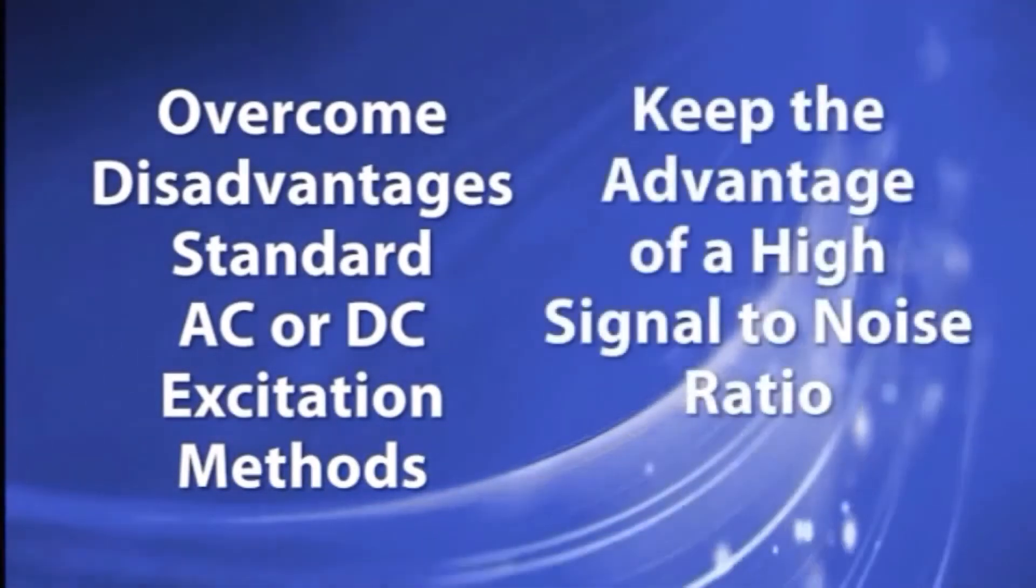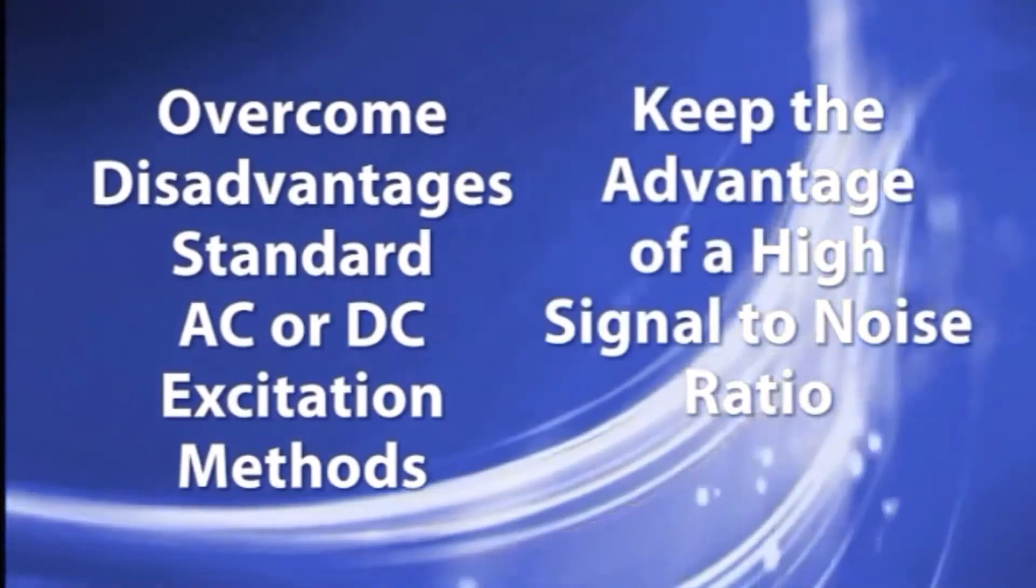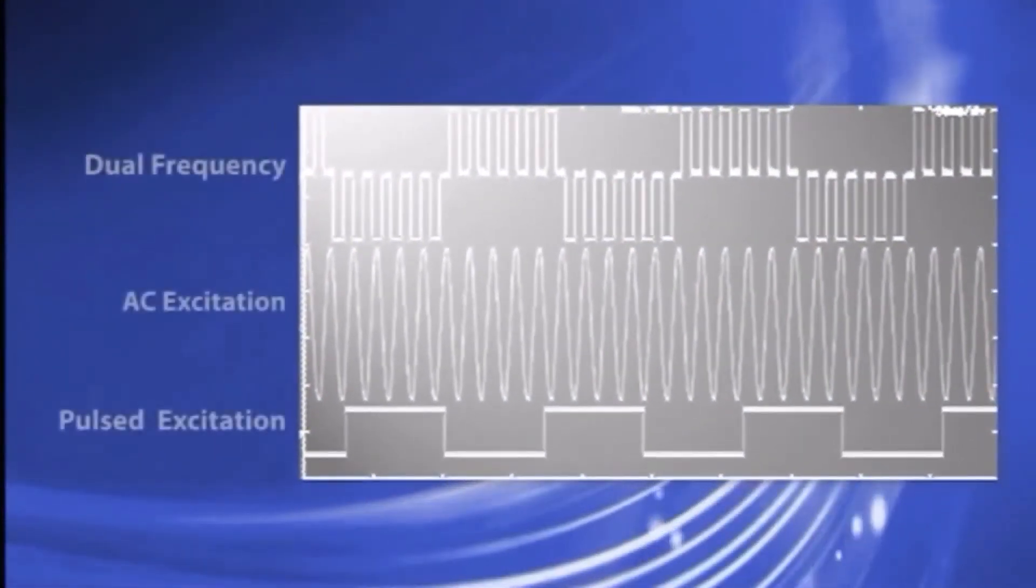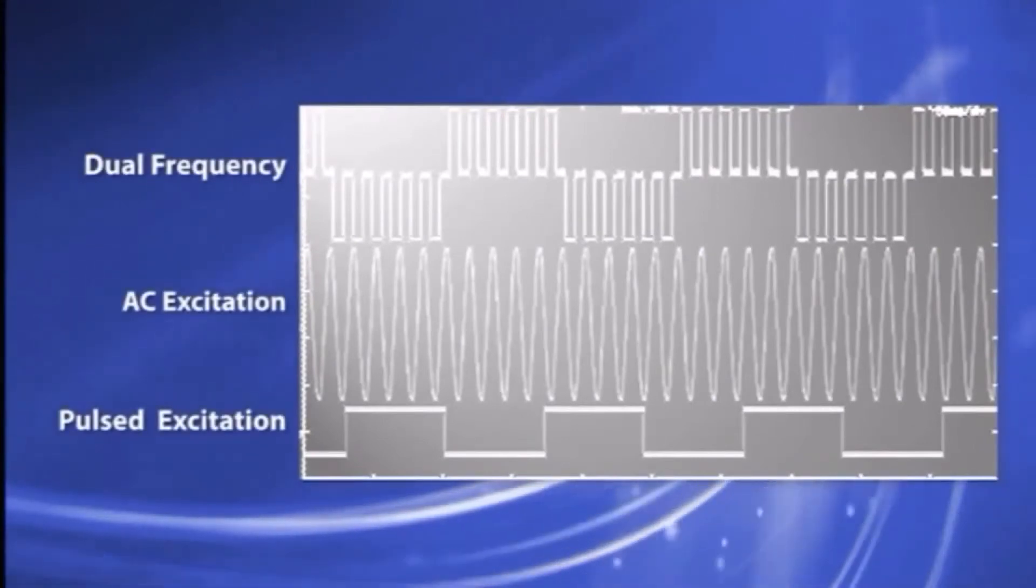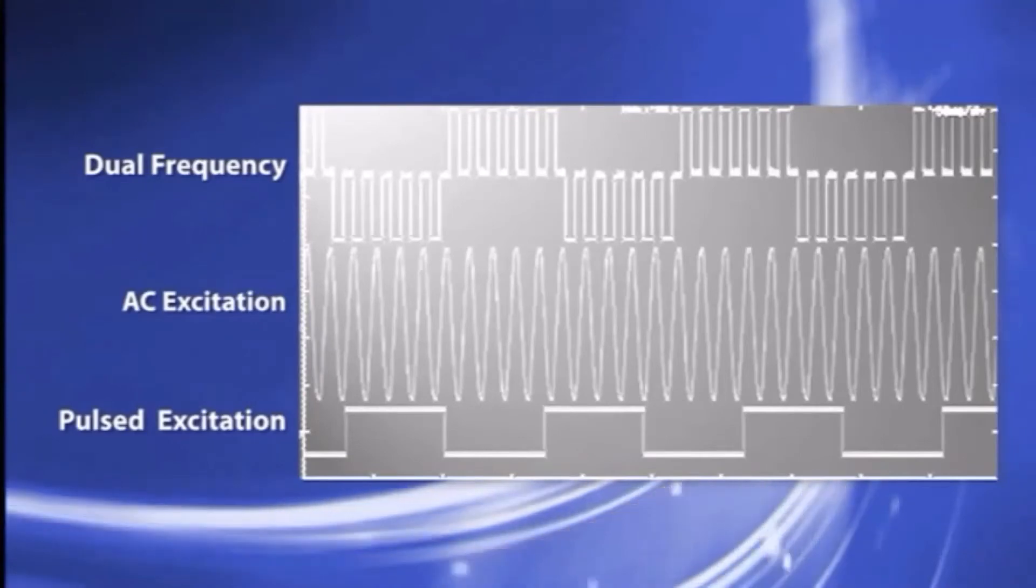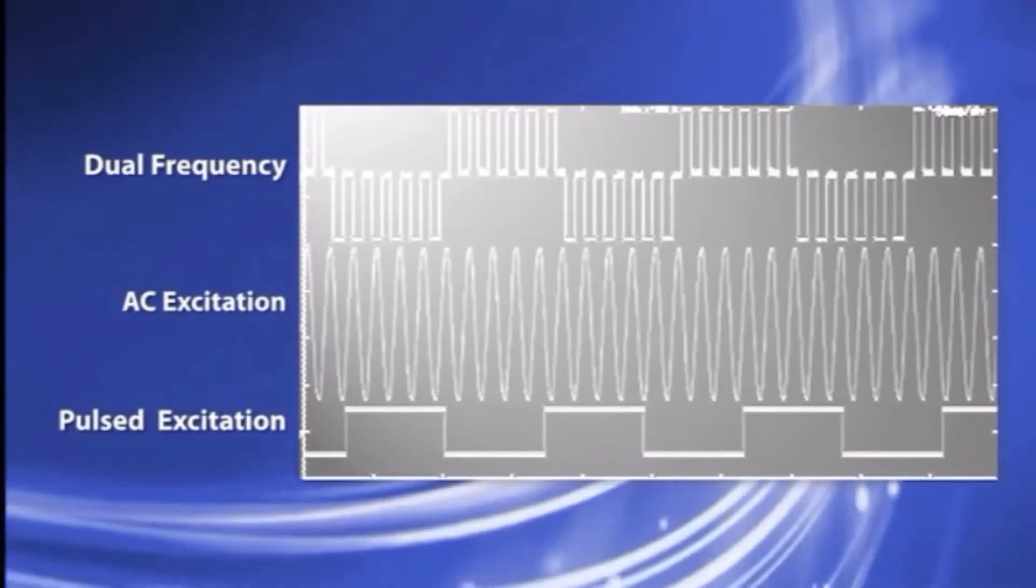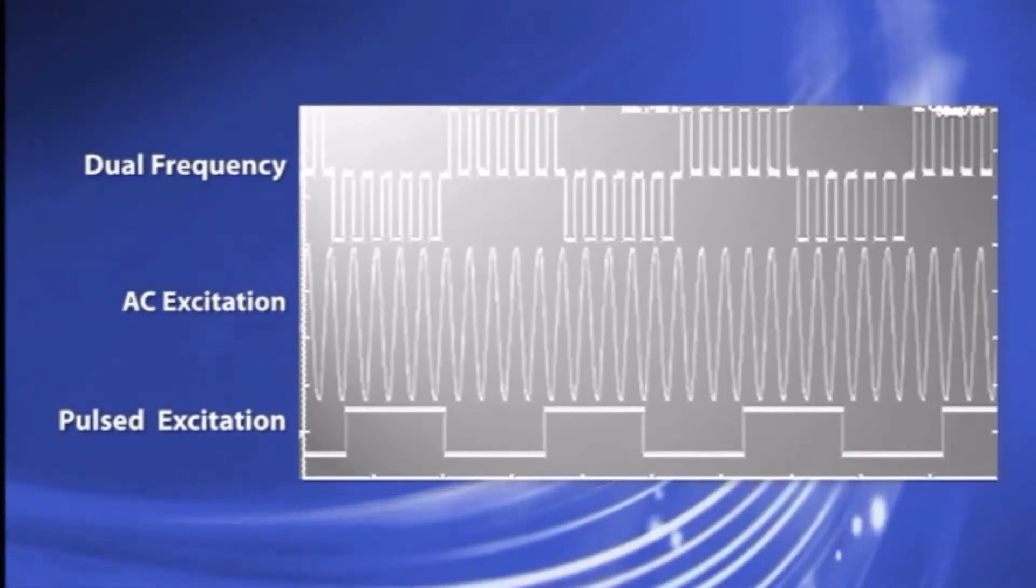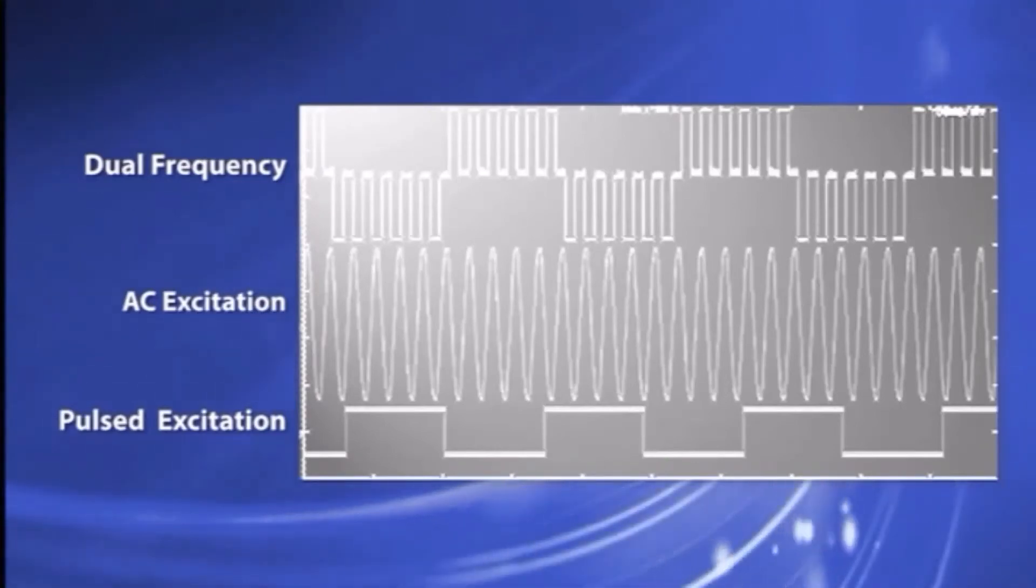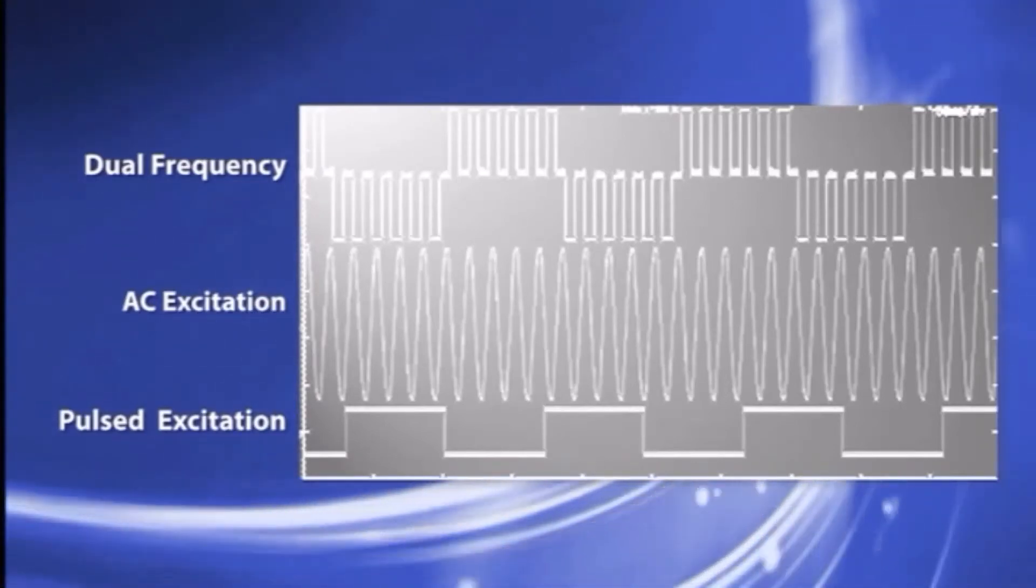To overcome the disadvantages of the standard AC and DC excitation methods and keep the advantage of a high signal-to-noise ratio, Yokogawa's patented dual frequency excitation is the ideal combination. Dual frequency excitation combines the positive benefits of both AC and DC excitation using both a high 75 hertz frequency and a low frequency excitation of approximately 6 hertz to drive the coils.